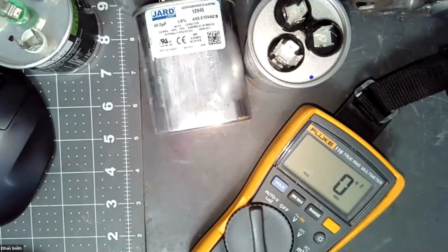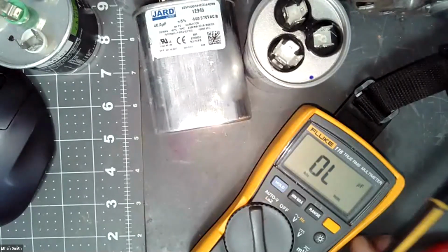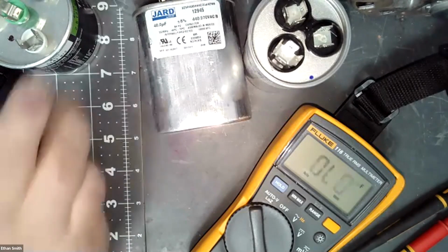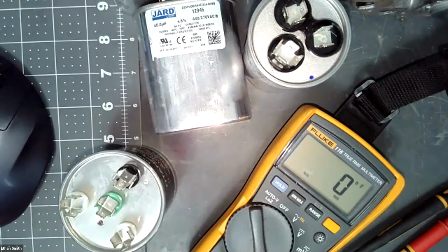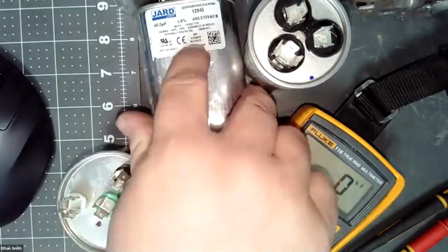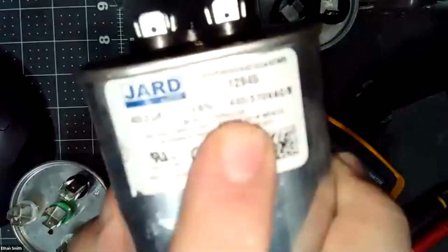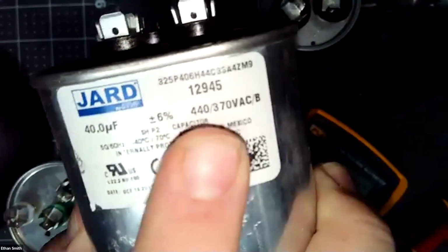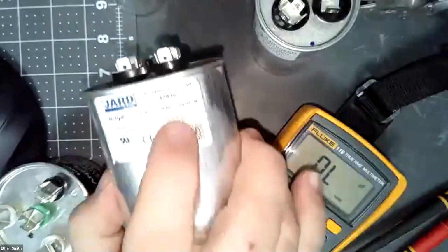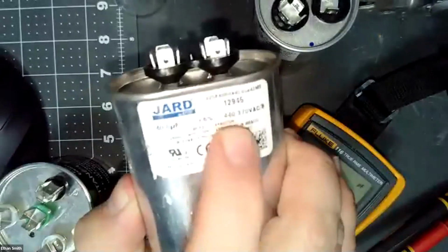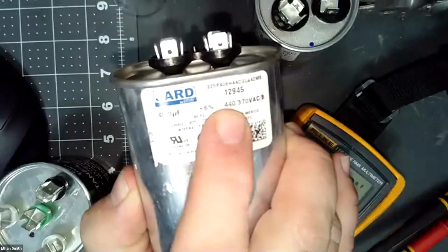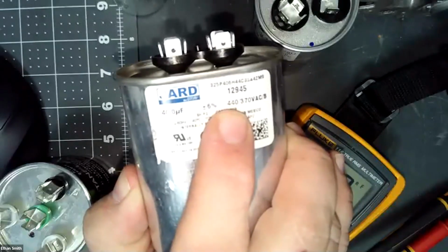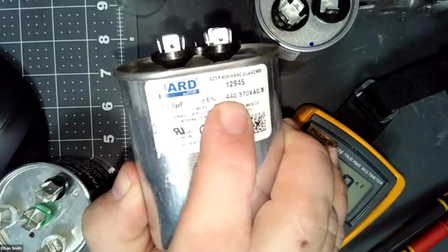The things we have to be careful of when we're replacing capacitors is we need to be plus or minus 5% of our capacitance rating. No more, no less than that. And we need to make sure that we match that voltage rating that's on the capacitor. And that voltage rating needs to be matched to our motors. So those are the 2 things. We can always go up on the voltage rating on the capacitor, but we can never go under the voltage rating of your motor or your previous capacitor.